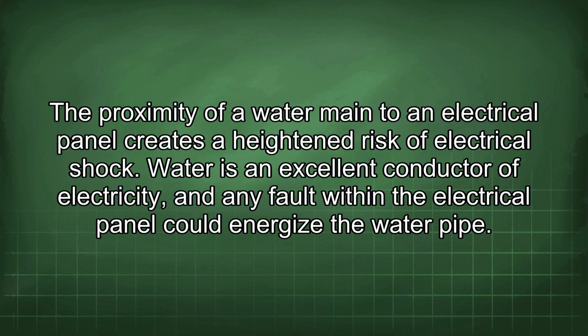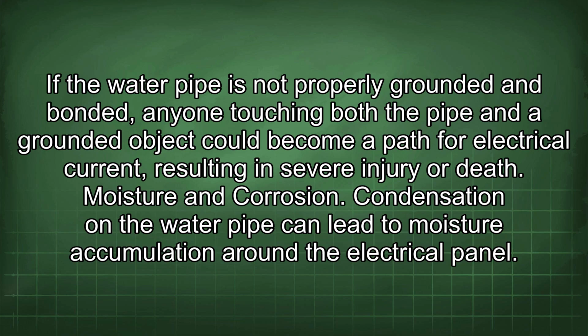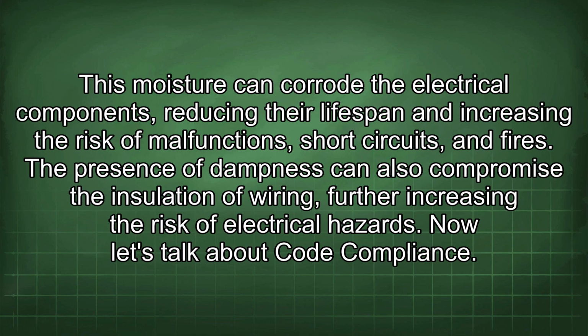energize the water pipe. If the water pipe is not properly grounded and bonded, anyone touching both the pipe and the grounded object could become a path for electrical current, resulting in severe injury or death. Moisture and corrosion. Condensation on the water pipe can lead to moisture accumulation around the electrical panel. This moisture can corrode the electrical components, reducing their lifespan and increasing the risk of malfunctions, short circuits, and fires.